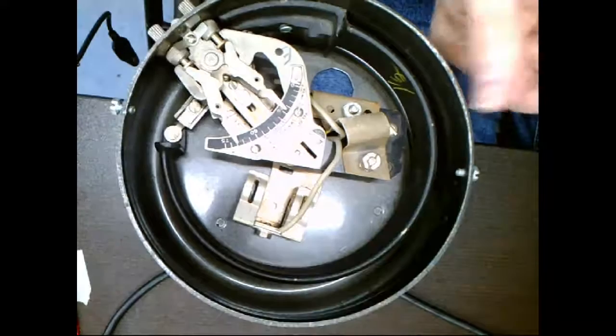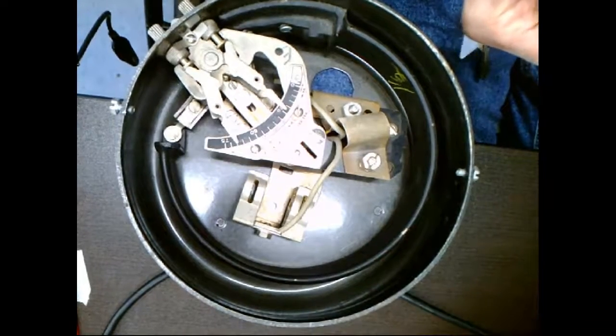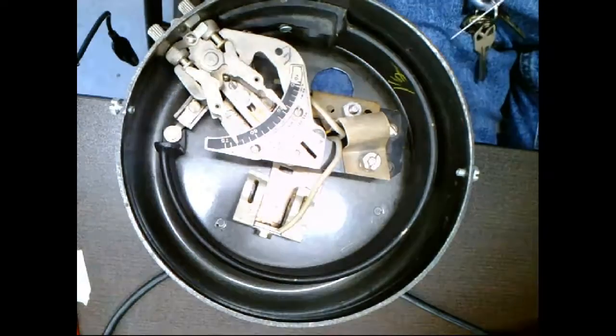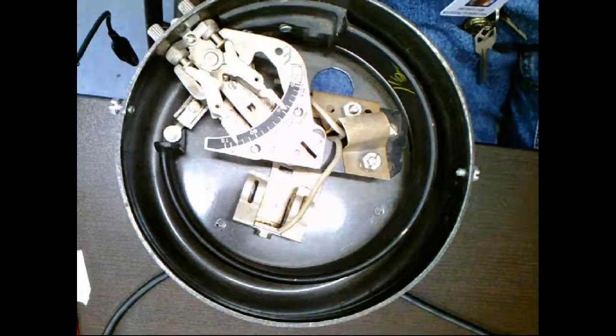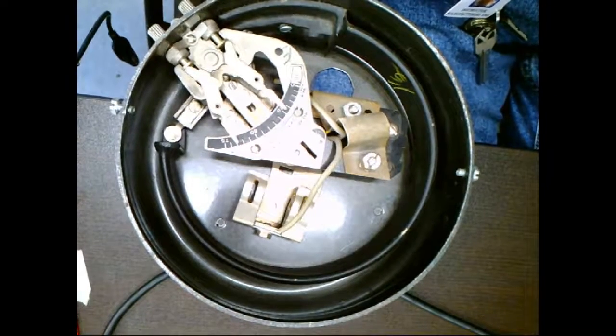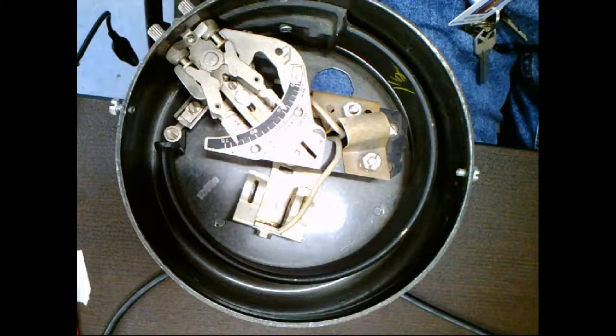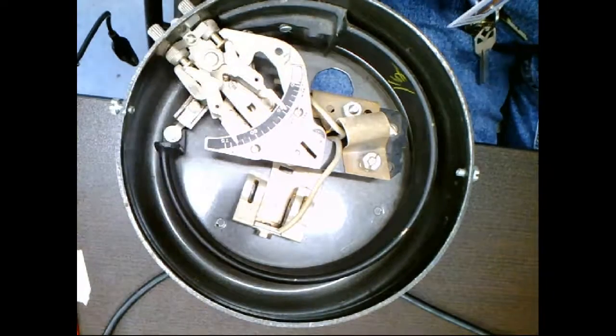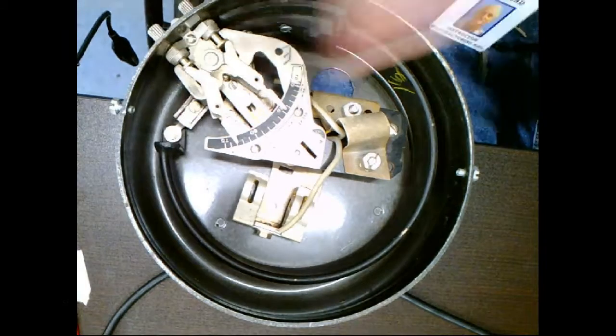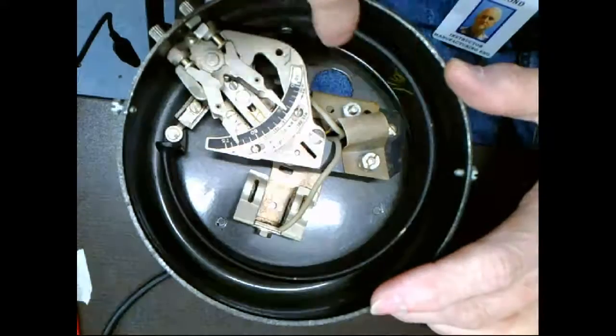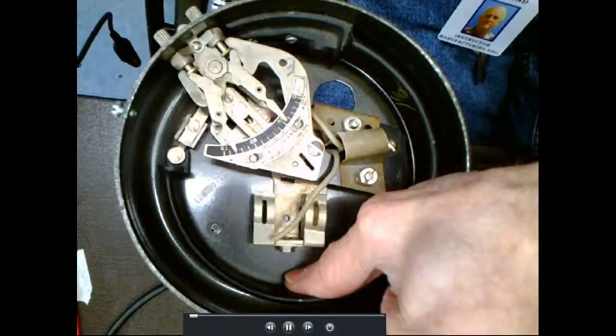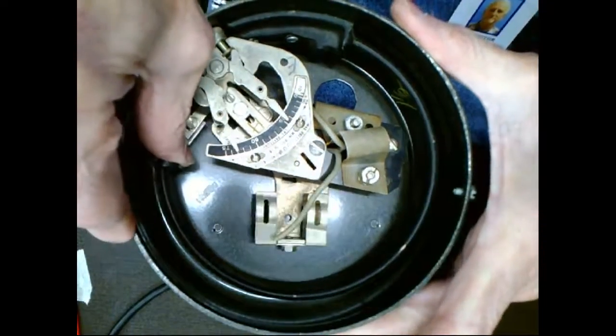You've played around with Bourdon tubes probably at a birthday party - you get those things that are all rolled up, and you put pressure in one side. What do they do? They unroll. You let them go and they automatically come back. That's a Bourdon tube. Well here's this Bourdon tube, this piece of metal, and when I put pressure down on the end, what's the tube going to do? It's going to try to straighten out.